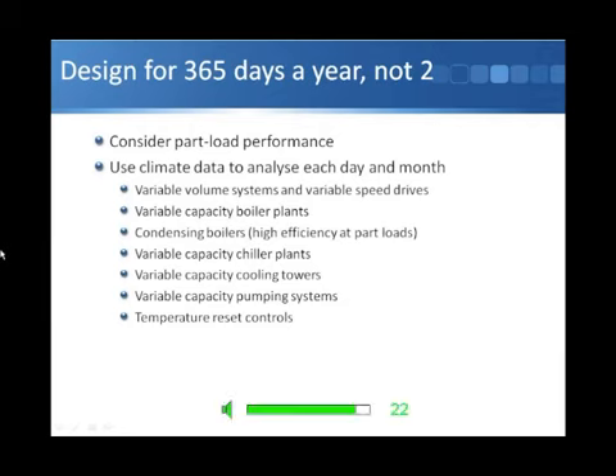And we need to have these variable systems in place so that we can reduce the amount of water flowing, the amount of air flowing around a building, and save energy, because we just don't need that quantity all the time. And as you can show in this slide, we really have to think about that across all of our plant: air conditioning, heating, cooling, pumping systems. And also think about resetting temperature levels. So in the winter, it might be perfectly adequate to come into a building at 20, 21 degrees C and feel warm, and that's good. When you're moving in summer, that building could be at 24 or 25 and feel comfortably cool. So we don't need to have the same set point all the time. So you need to understand how to make that happen.